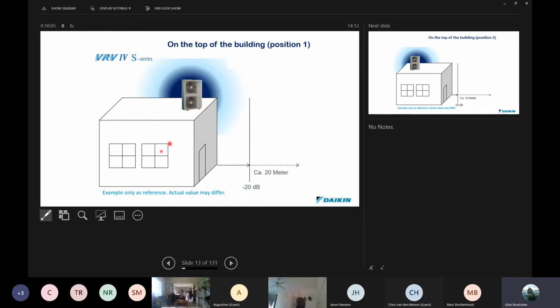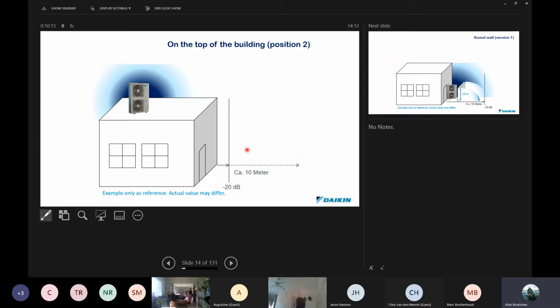But if this was the tallest building in an area, this actually might be the option to go for, because the breakout is up mostly and away from the building and not going to affect the people that are living lower down. We could move the unit further back, okay, and over here you can see that this time now we've basically deadened all the sound problems around the side of the building. Okay, so moving the units around to get a better position can be one way of eliminating it.